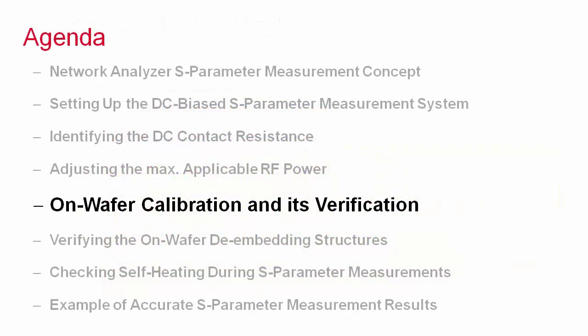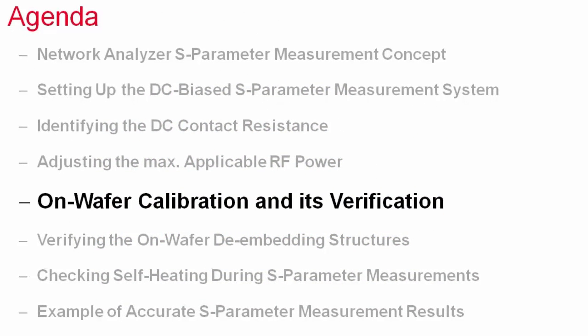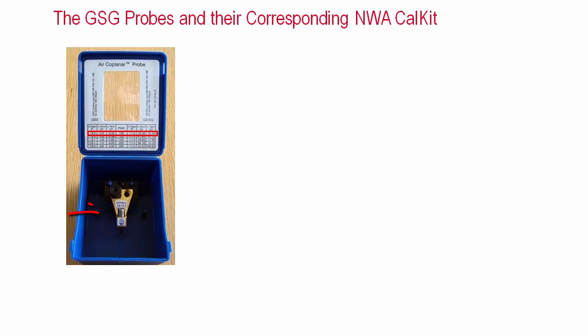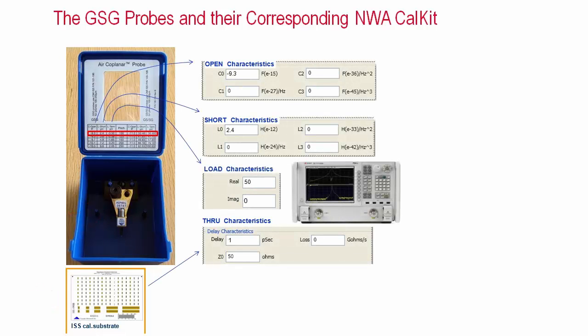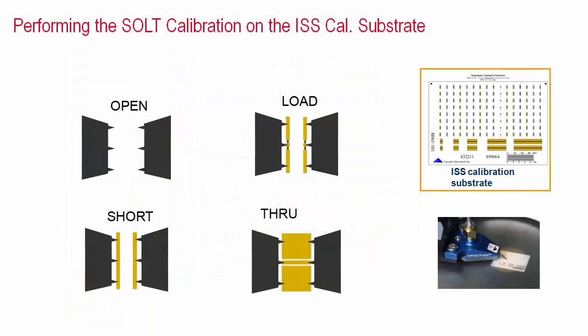Once this signal level has been identified, we are ready to perform the network analyzer calibration, applying this power level. First of all, the applied ground signal ground probe and the probe calibration substrate must correspond. The cal standard definitions provided by the probe manufacturer describe the non-idealities of the calibration standards and need to be entered to or selected by the network analyzer's calibration program. After that, the calibration can be performed.